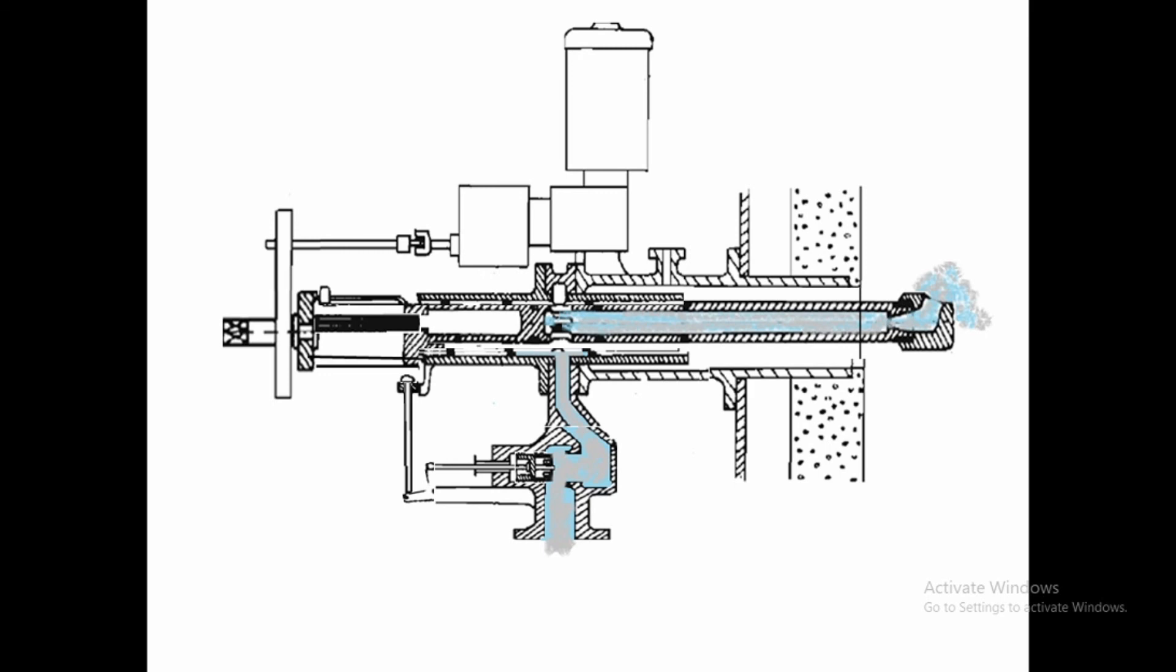At this point, it is locked. At the operative point, the spindle is opened and locked, and it starts revolving the spindle. As the spindle is revolving, the nozzle is also revolving at 360 degrees. It also cleans the soot on the tubes.